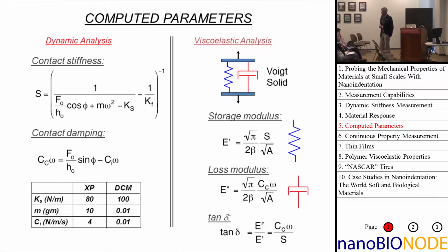How do you find those numbers for the calibration of the machine? Most machines, or at least the machines we use, have internal procedures that you run to find the machine constants.